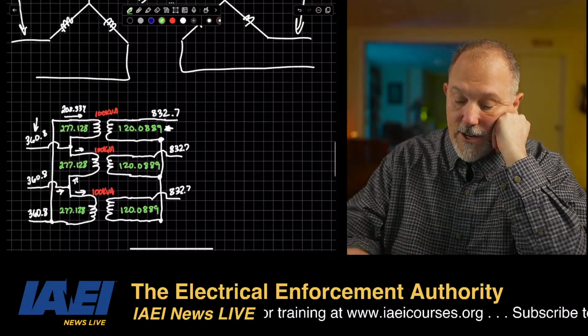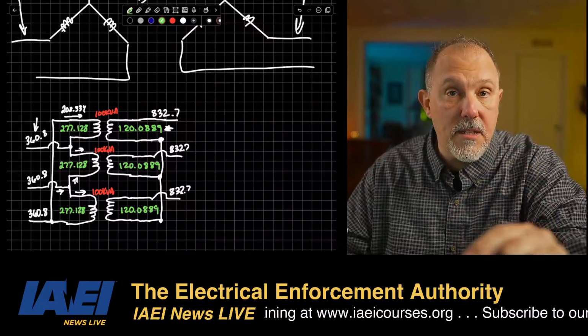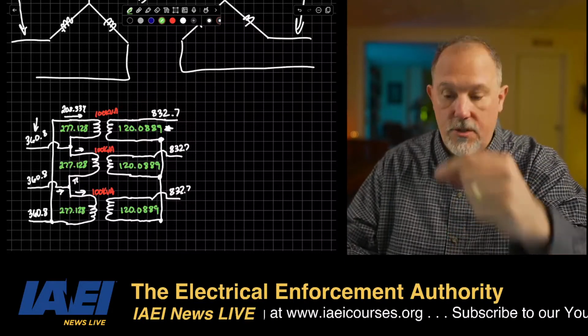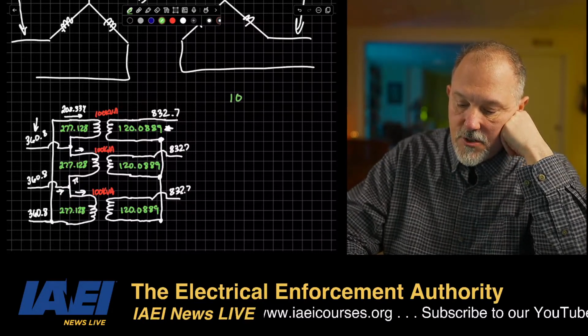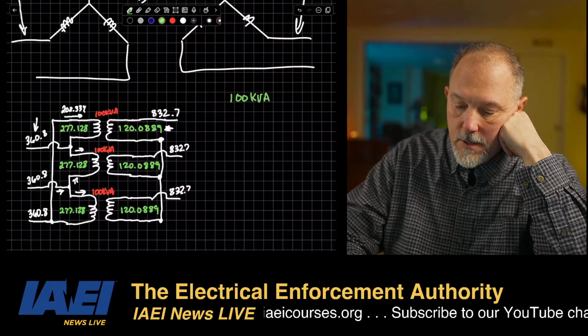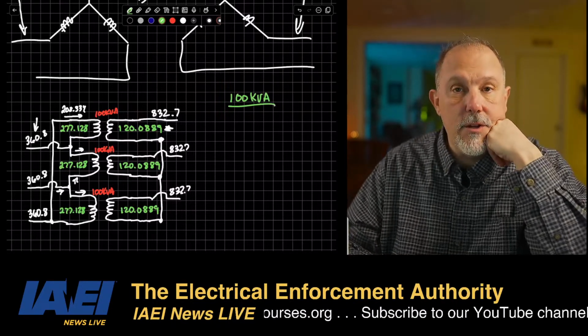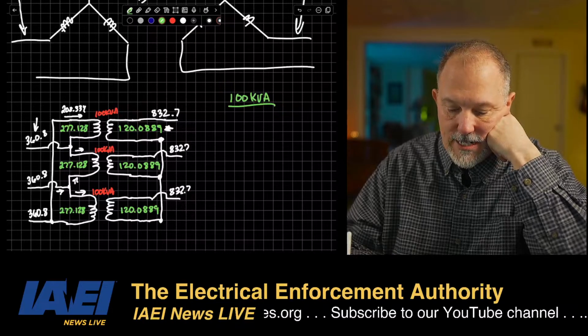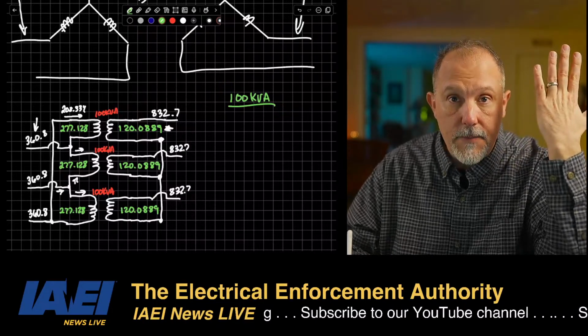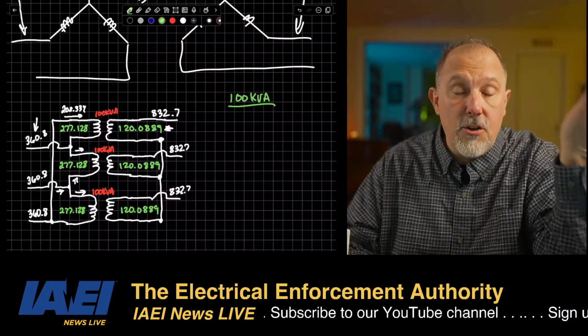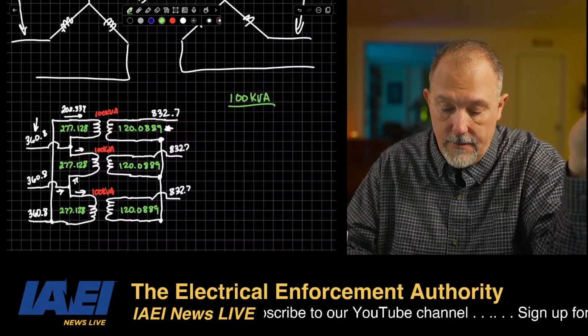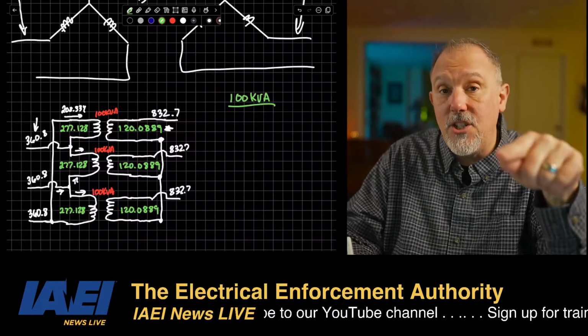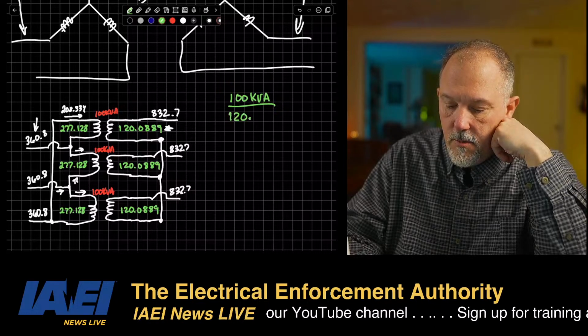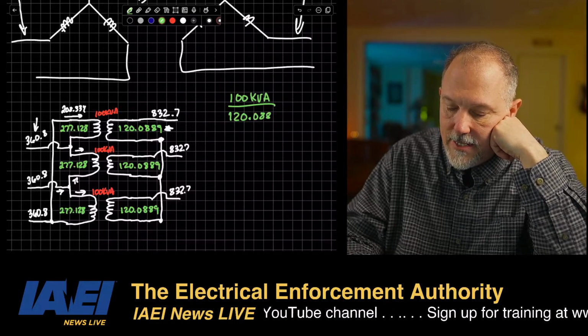Now I have 100K. I'm going to do this based upon the single phase transformer. I have a 100 kVA transformer. To get to the full load amps on the secondary, I don't divide by the square root of 3. I don't divide by 3. It's a single phase transformer. It's 100 kVA. I have to divide it by the voltage, which is 120.0889.